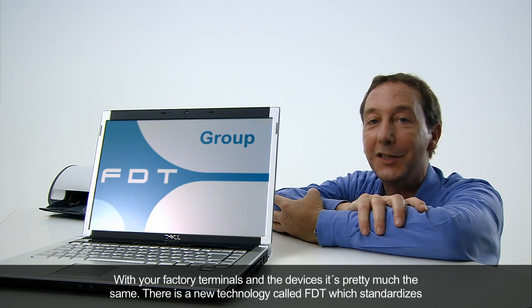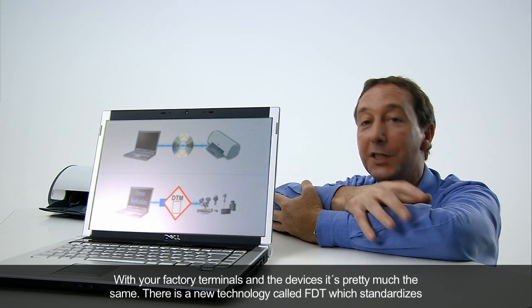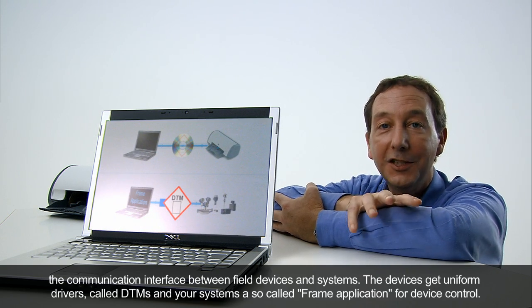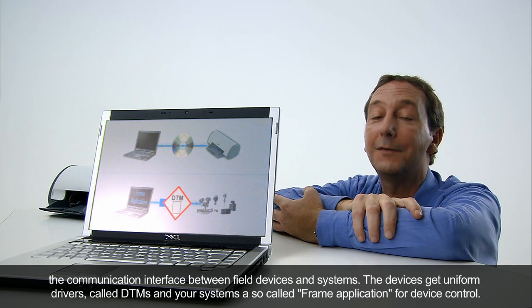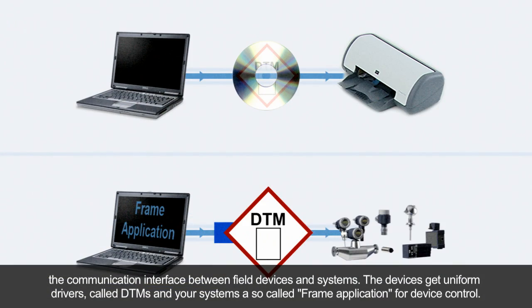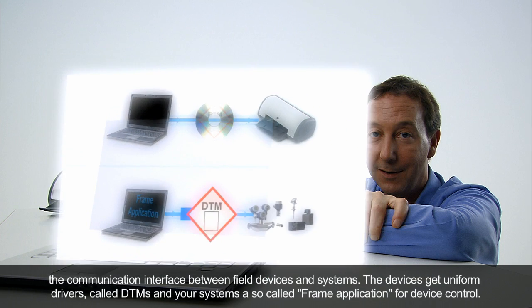There's a new technology called FDT, which standardizes the communication interface between field devices and systems. The devices get uniform drivers called DTMs, and your systems a so-called frame application for device control.